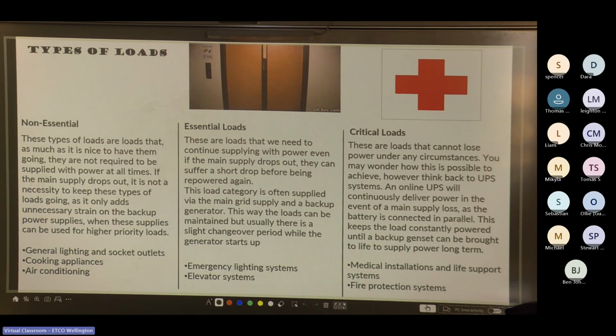So you got your essential loads, so the loads that need to continue supplying with power, even if the main supply drops out. They can suffer a short drop before being repowered again. This load category is often supplied by the main grid supply and a backup generator, which is why the loads can be maintained, but usually there is a slight changeover period. So they're your emergency lighting systems and your elevator systems. Although a lot of elevators these days also have a battery backup system installed, mostly enough to get the elevator from between floors to the nearest floor. And that's what they're set up to do. As soon as they detect that the mains has disconnected, the battery will kick in and it'll take the elevator to the nearest floor, open the doors, and let you out.